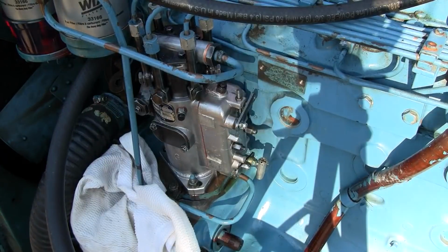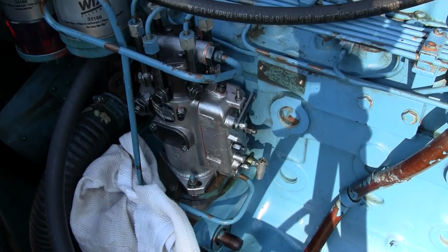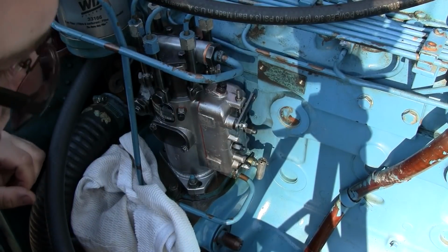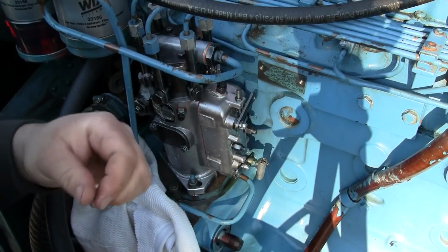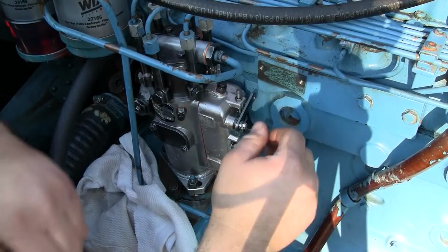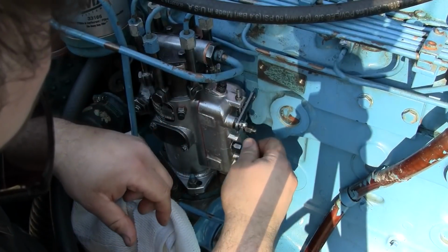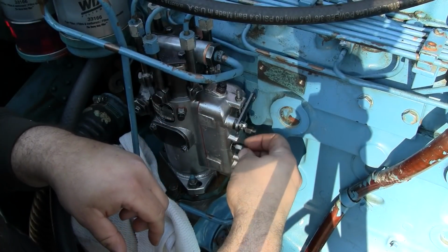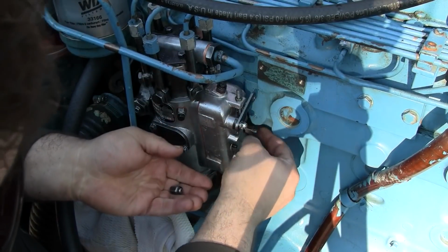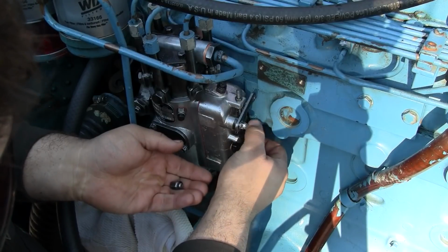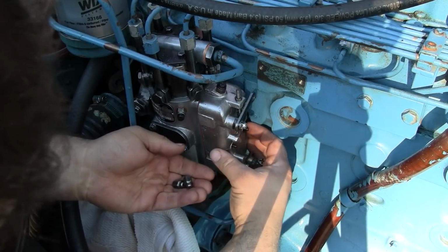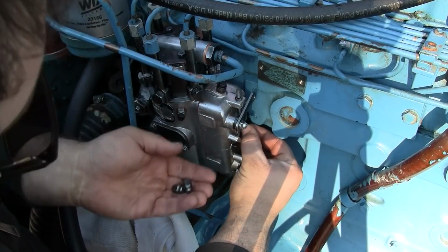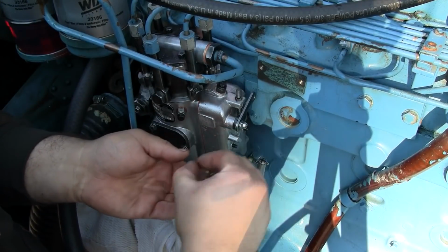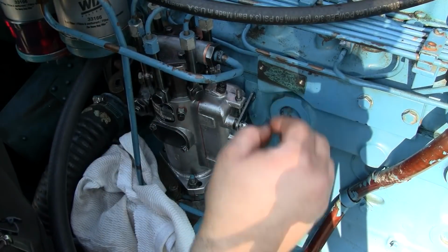Okay, so we're going to try to adjust the sensitivity of the governor here. We're going to move that anchor point on the governor lever closer to the pivoting point. In order to do that, I've removed the shutdown solenoid and already loosened and drained all the fuel out of the governor housing. Made quite a mess. This is an unfortunate position for this governor, or for this injection pump.